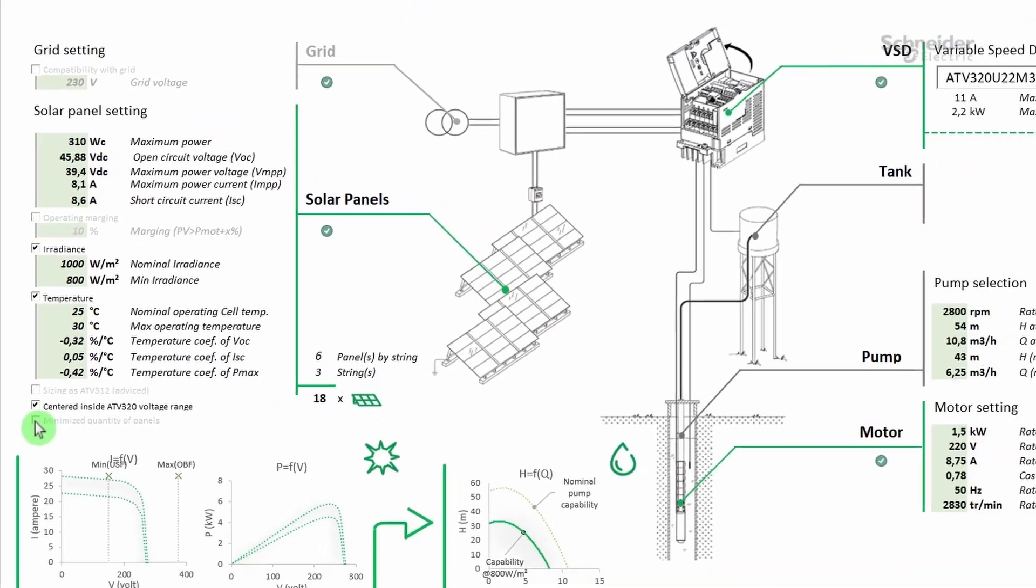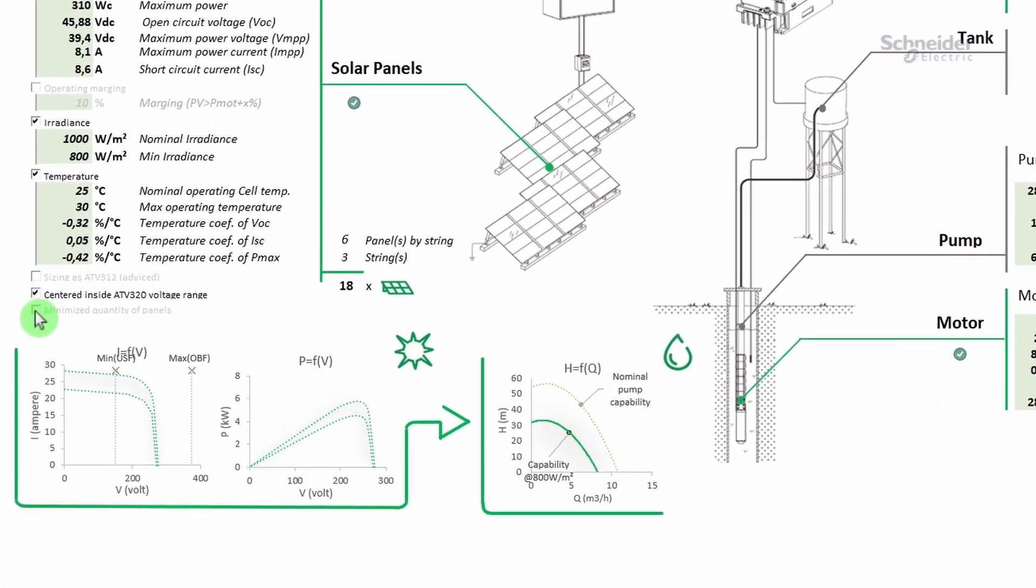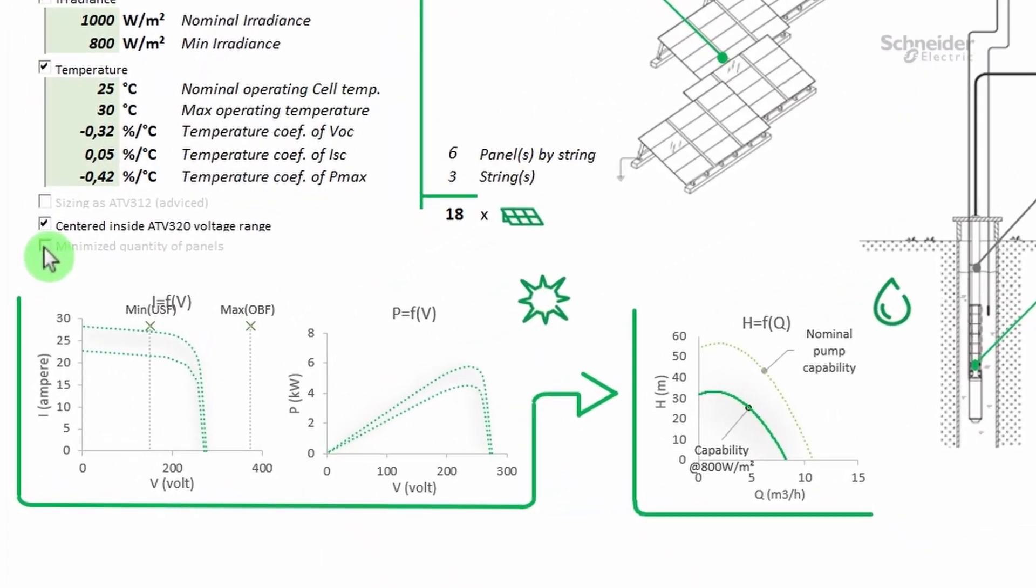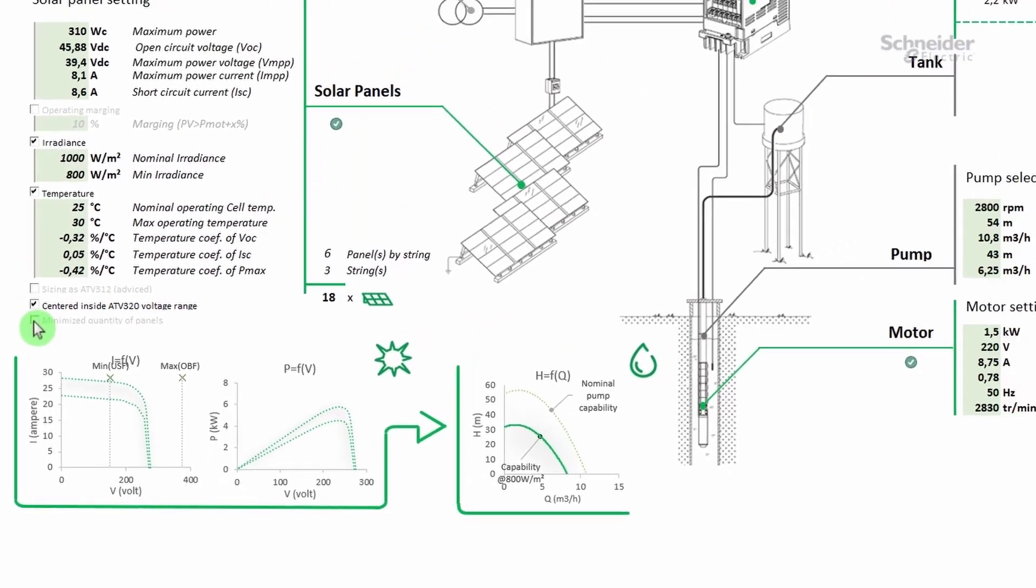This solution is acceptable. This solution is acceptable, but the flow curve is not good. To be sufficient, the capability curve must match or be as close as possible to the nominal pump capability curve.